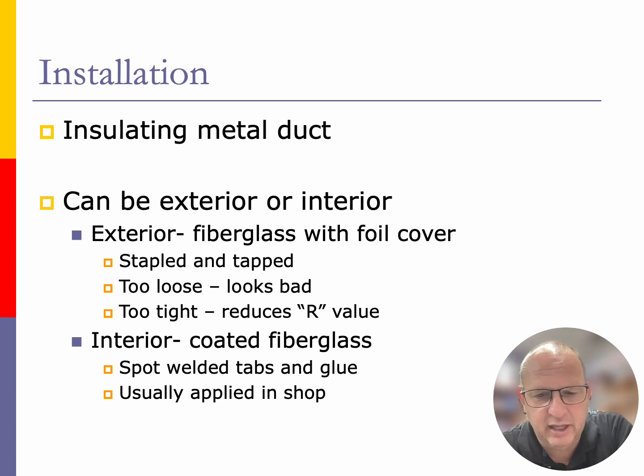The exterior insulation, as I will talk about, and as you will see in the next couple of slides, has to be wrapped on the pipe, not too loose or it looks really bad, not too tight or you lose the R value of that pipe, but just the right amount of tightness so that it fits around the ductwork. Anywhere that there is a really tight connection on this insulation to the metal, you're going to get more heat transfer, because you're smashing that fiberglass insulation down from being 1 inch to maybe being 1/8 of an inch on that particular duct.